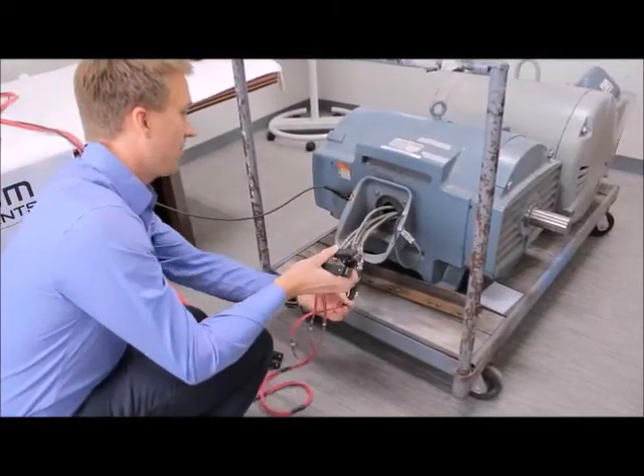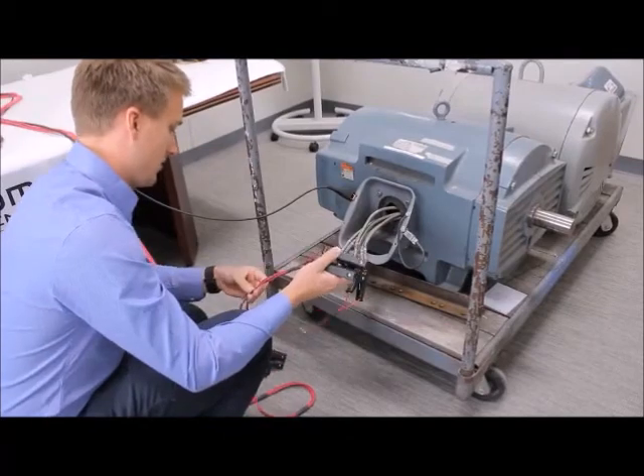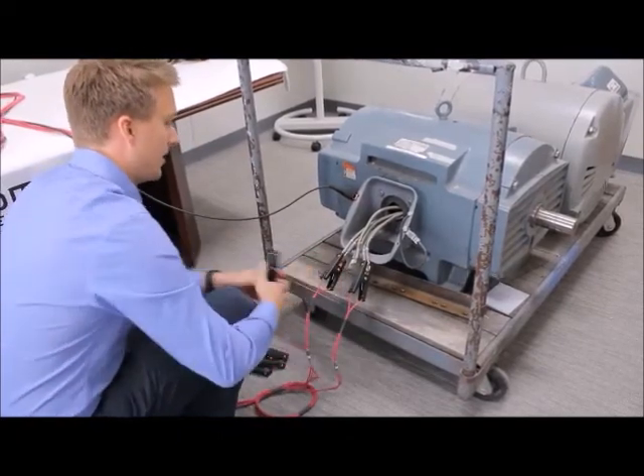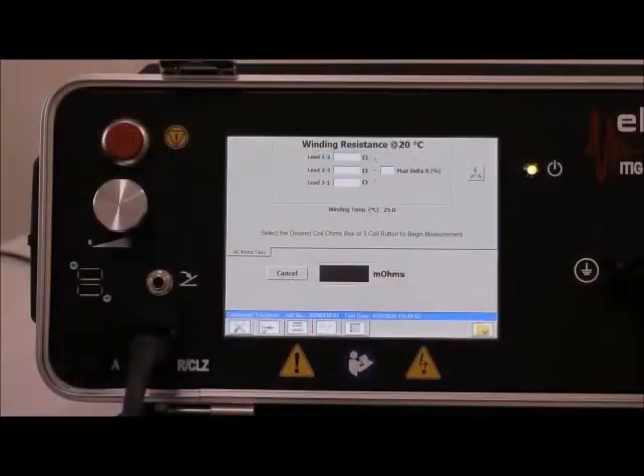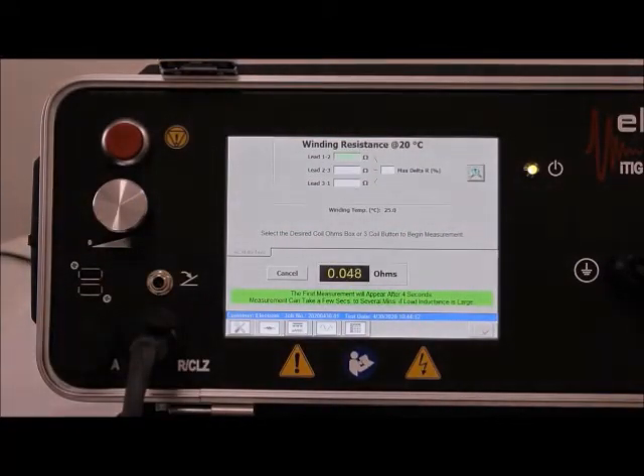Lead 1 to phase 1, lead 2 to phase 2, lead 3 to phase 3. And click the start coil symbol. The instrument will now go through and measure the winding resistance in lead 1 to 2, 2 to 3, and 3 to 1, and calculate the max delta R. If the delta R is greater than our limit, it will clearly indicate the failure.